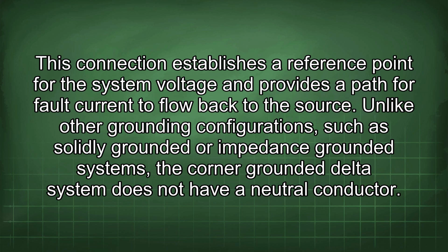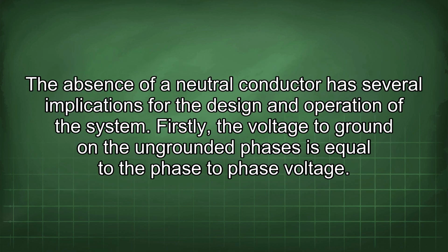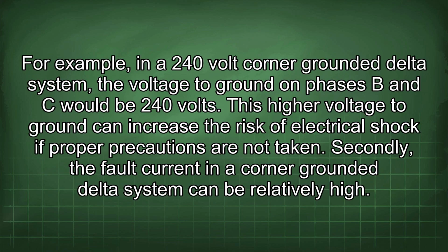Unlike other grounding configurations, such as solidly grounded or impedance-grounded systems, the corner-grounded delta system does not have a neutral conductor. The absence of a neutral conductor has several implications for the design and operation of the system. Firstly, the voltage to ground on the ungrounded phases is equal to the phase-to-phase voltage. For example, in a 240-volt corner-grounded delta system, the voltage to ground on phases B and C would be 240 volts. This higher voltage to ground can increase the risk of electrical shock if proper precautions are not taken.